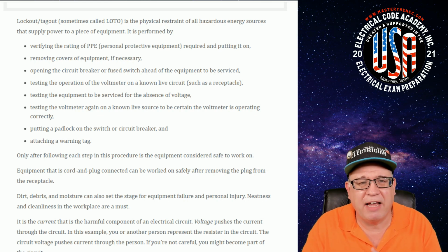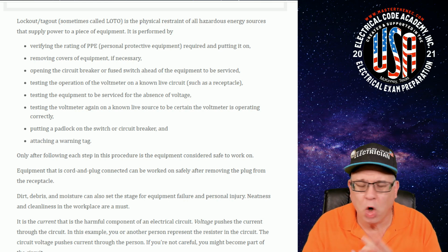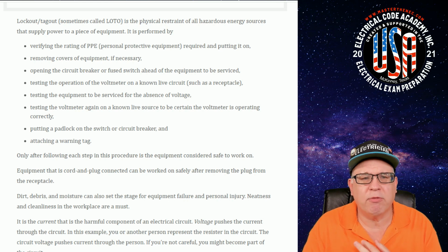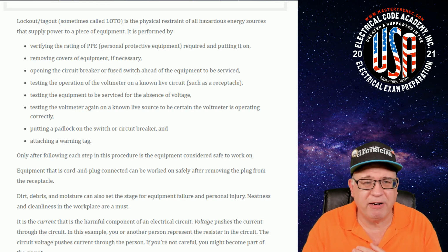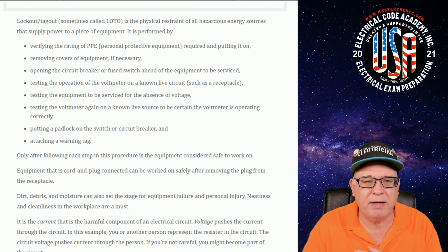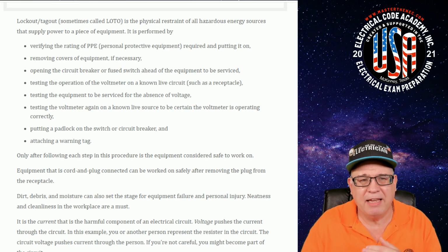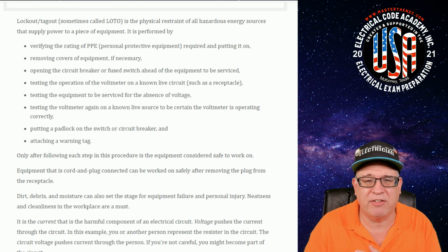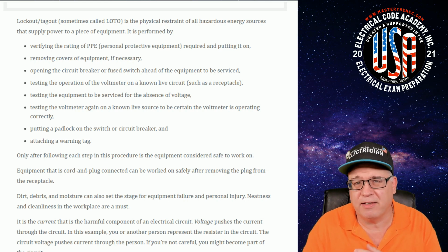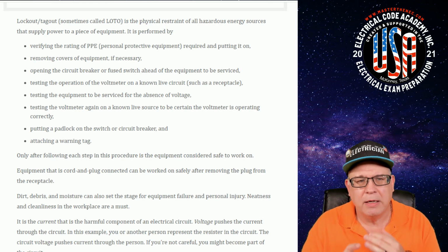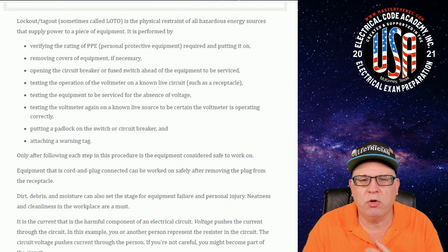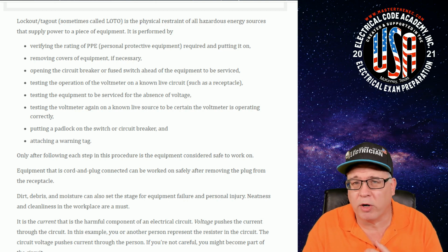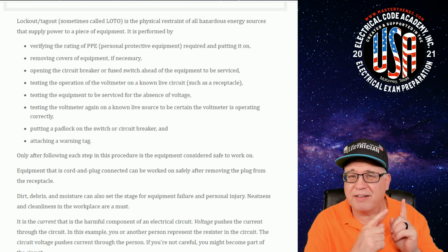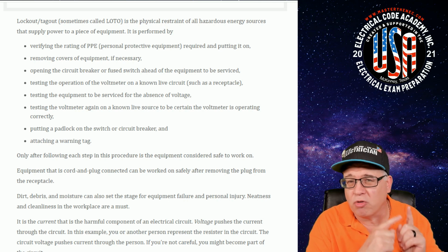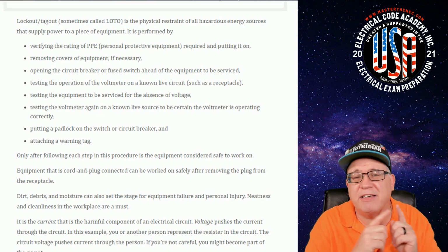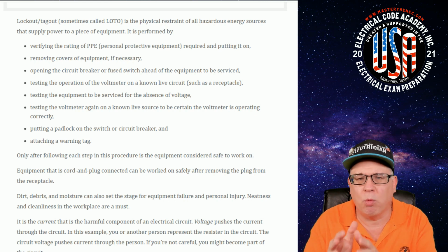So verify the ratings for PPE and know when to use it. If you have to remove covers on equipment, be very careful and cautious doing so, since it exposes live parts in the process of de-energizing or verifying the system has been de-energized. Open the circuit breaker or fuse switch ahead of the equipment you'll be working on. That's where your lockout tagout takes place upstream, to make sure you lock it out, tag it out, and de-energize the circuit before you work on something.